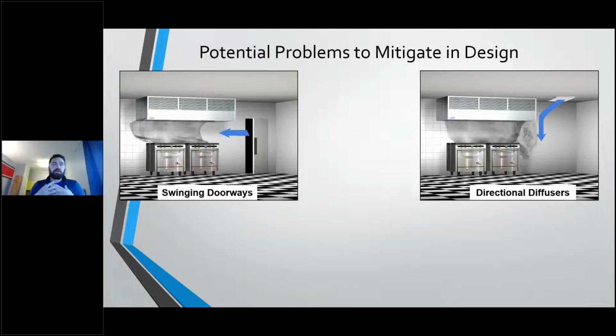It's also best practice, or the rule of thumb that I always bring up, is not to have any diffuser within 10 feet of the hood. Now, I know that a lot of people hear that and they kind of laugh at me and they say, Mike, you've seen these kitchens that we're doing. I have to have diffusers within 10 feet of the hood. And I get that. There's ways that you just can't get around it. The best practice that I've thrown out around the country is not within 10 feet of a hood, and just keep them as far away as possible on those diffusers.